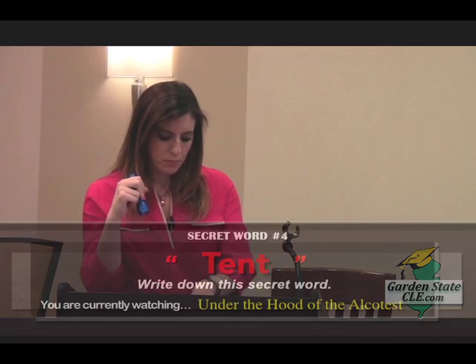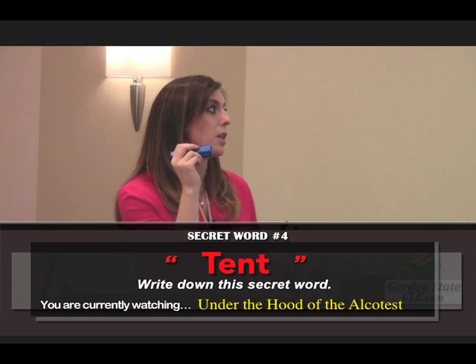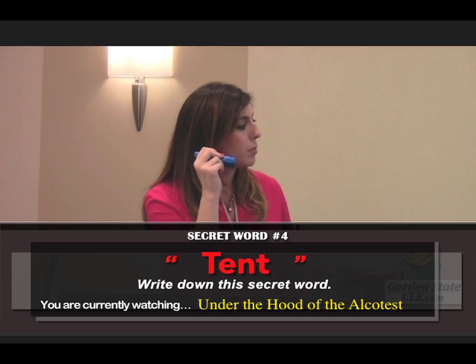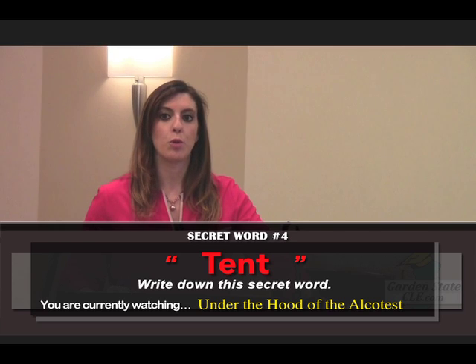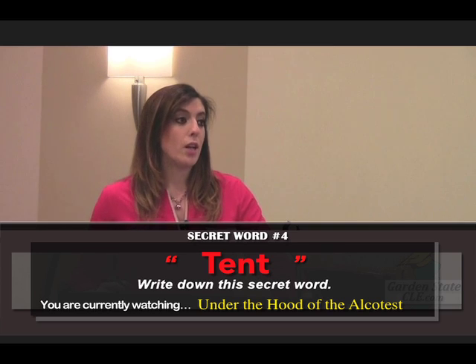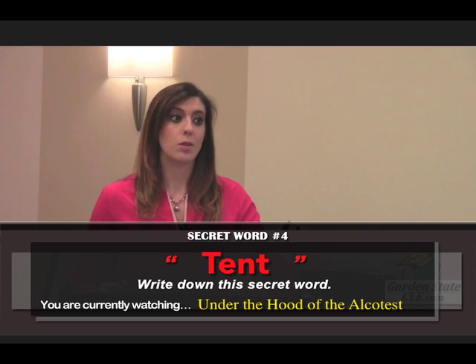You're going to get a second new standard solution report unless your client's test was within 30 days or 25 tests of the one that happened at the time of calibration. You'll get a second one. By the way, the average in New Jersey is 12 or 13 tests before they have to change the solution. Never seen one make it to 25. Right. So this one here, it's got a different file date than calibration date. It's probably going to be the same solution control lot. But here you'll see they don't put in the temperature probe serial number. The rationale, I think, is that they're not supposed to touch it. Some of the prosecutors here could probably tell you that the police departments are told not to touch it. And it supposedly is the same one that's on the instrument.